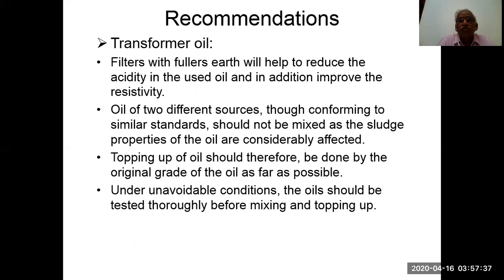Oil of two different sources, though conforming to similar standards, should not be mixed as the sludgy properties of the oil are considerably affected. Topping of the oil should therefore be done by the original grade of the oil as far as possible. Under unavoidable conditions, the oil should be tested thoroughly before mixing and topping up.